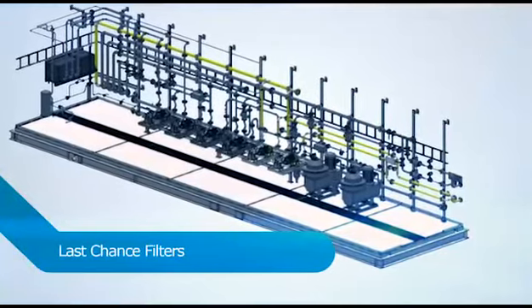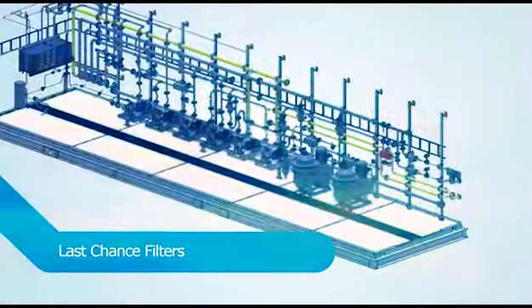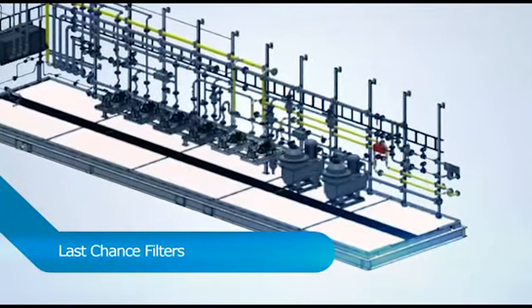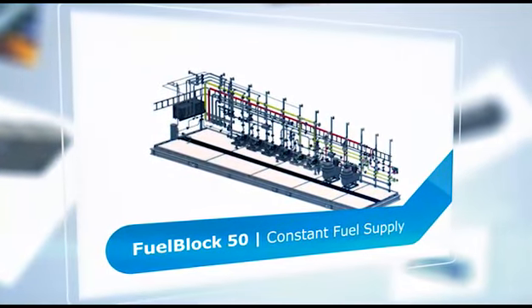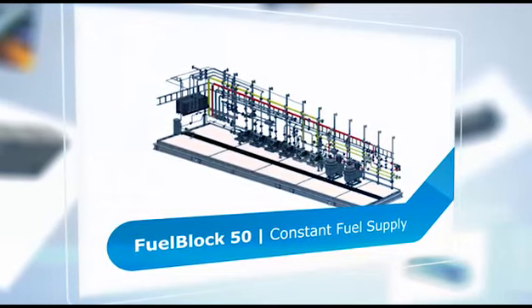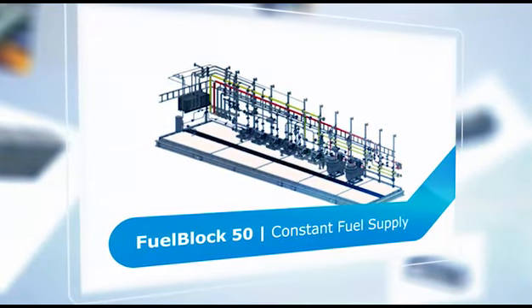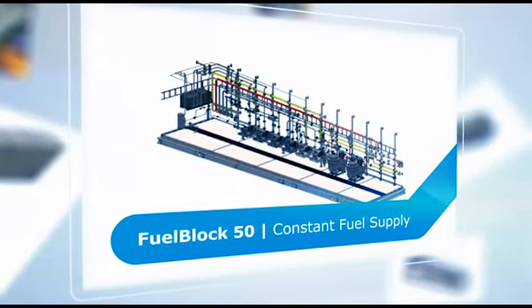Accumulators are provided with the last chance filters to reduce fluctuations in pressure at the turbines. Clean fuel return lines in the fuel block are fitted with pressure control valves and flow metering to ensure constant delivery pressure and flow availability at the turbine connection.